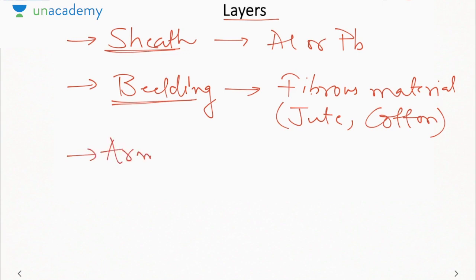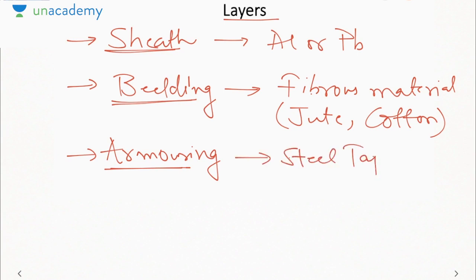Next is armoring. As the name implies, it acts as an armor, that is, to protect the cable. So how does it protect the cable? It protects the cable from any mechanical damage. When the cable is being transported, it can incur mechanical damage, and whenever you are laying it down beneath the earth's surface, it can break down or suffer damages. So to protect the insulation and the conductor from getting damaged, we use an outer layer called armoring. So it will prevent any mechanical damage in the cable. It is generally made of steel tape. That is the material that is used to make the armoring layer.